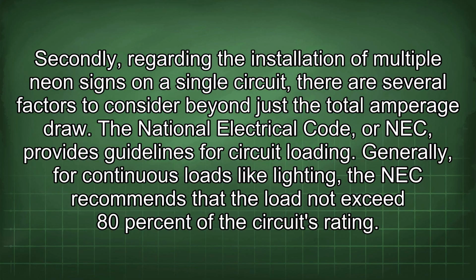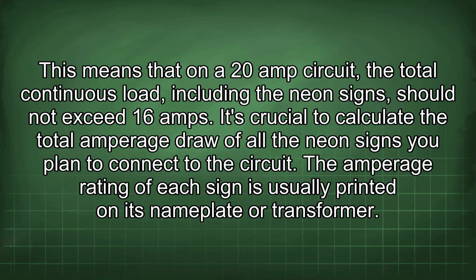Secondly, regarding the installation of multiple neon signs on a single circuit, there are several factors to consider beyond just the total amperage draw. The National Electrical Code, or NEC, provides guidelines for circuit loading. Generally, for continuous loads like lighting, the NEC recommends that the load not exceed 80% of the circuit's rating.